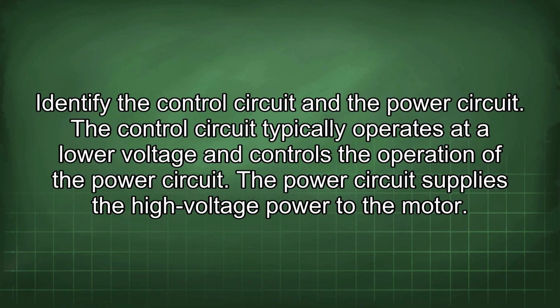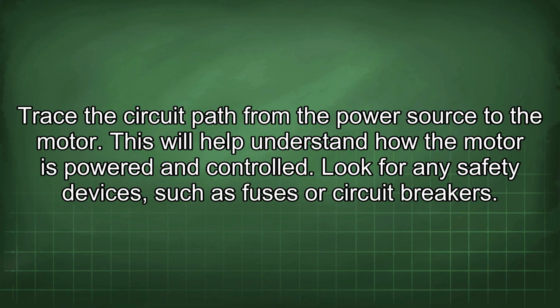Identify the control circuit and the power circuit. The control circuit typically operates at a lower voltage and controls the operation of the power circuit. The power circuit supplies the high voltage power to the motor. Trace the circuit path from the power source to the motor. This will help understand how the motor is powered and controlled.